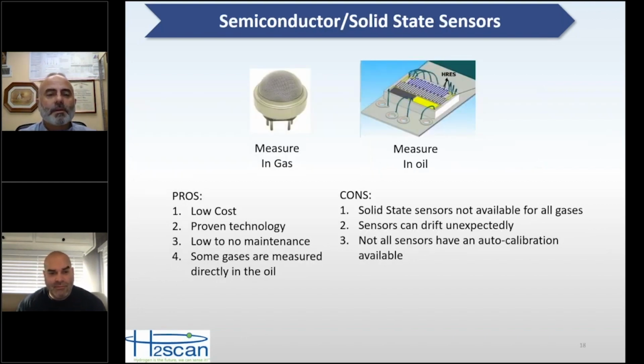Okay, so the other technology that is gaining popularity today is semiconductor or solid state sensors. There are a variety of sensors available. Most of the sensors available in the market today measure the different gases in the gas phase. So the gas still needs to be separated from the oil, typically through some type of membrane. Vacuum extraction is being used by one vendor that I'm aware of and is yielding excellent results. But in order to measure the gas in the gas phase, again, you do need to pull the gas out of the oil, get the gas out somehow.